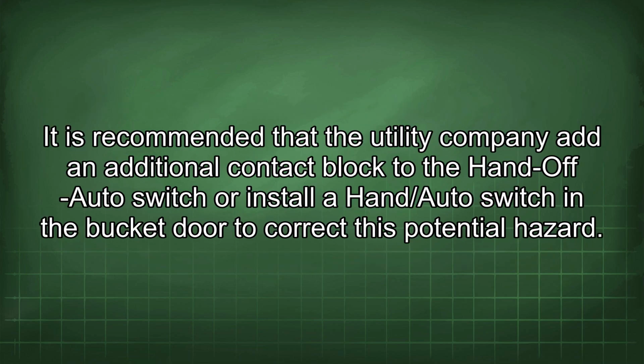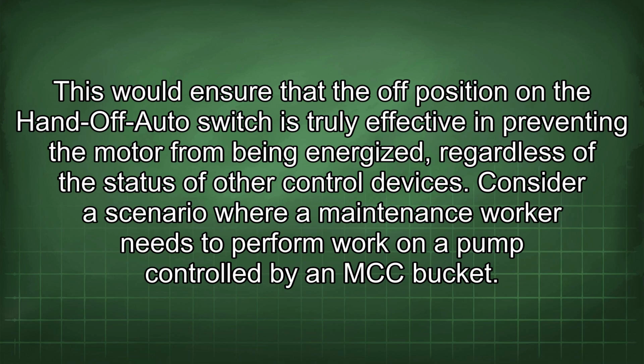It is recommended that the utility company add an additional contact block to the hand-off auto switch or install a hand/auto switch in the bucket door to correct this potential hazard. This would ensure that the off position on the hand-off auto switch is truly effective in preventing the motor from being energized, regardless of the status of other control devices.